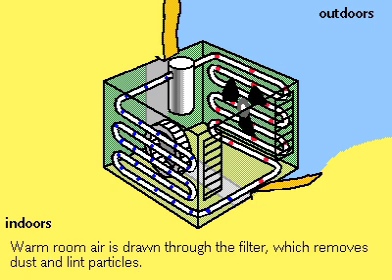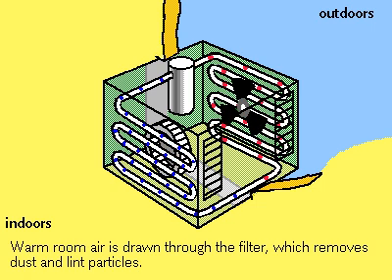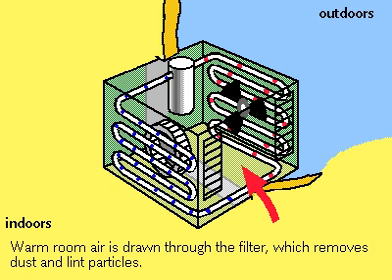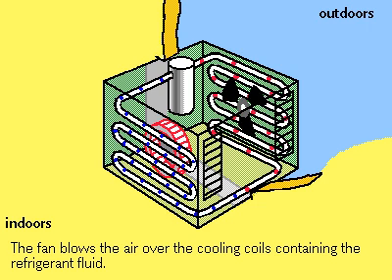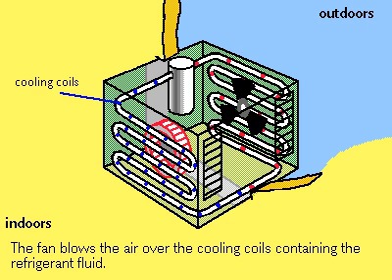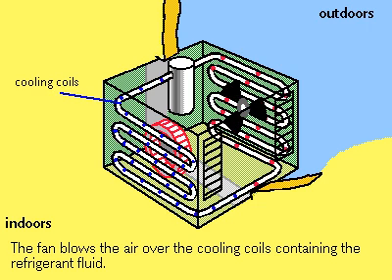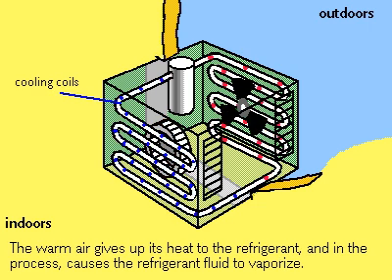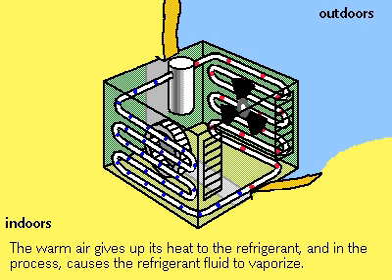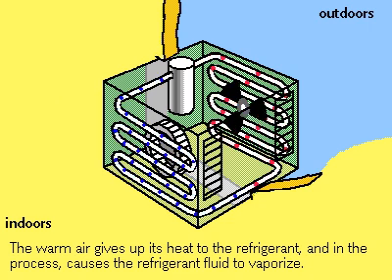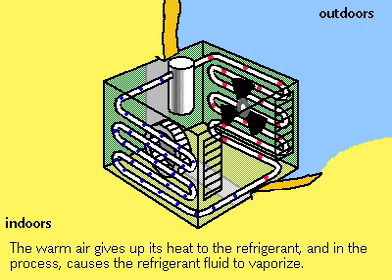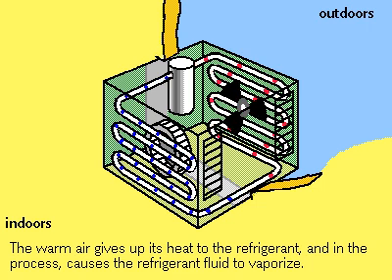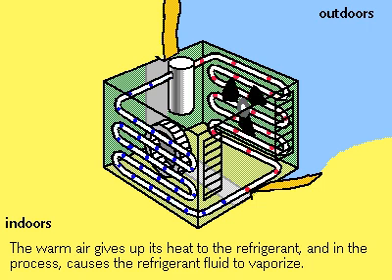Warm room air is drawn through a dust filter by a fan, then blown over the cooling coils, which circulate the refrigerant in its liquid state. As the room air flows by the coils, it causes the liquid in the coils to evaporate, and in the process heat is absorbed by the refrigerant as it turns to gas. The cooled air is blown back into the room.